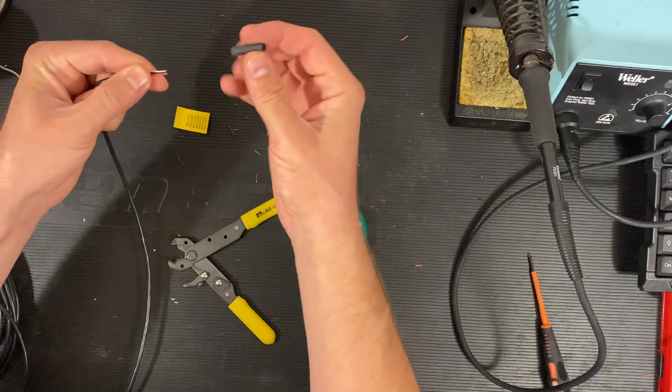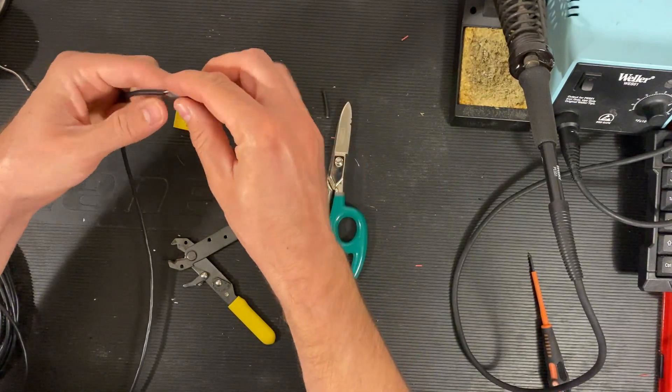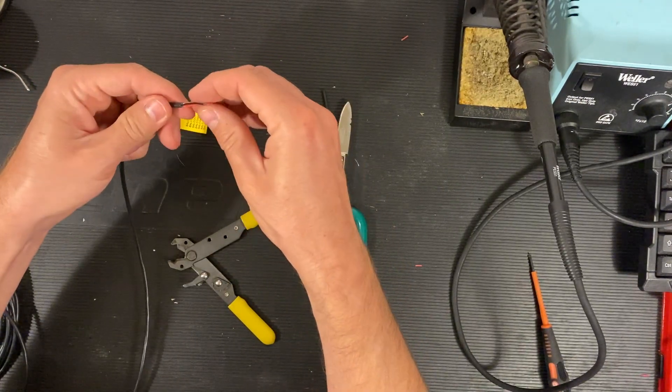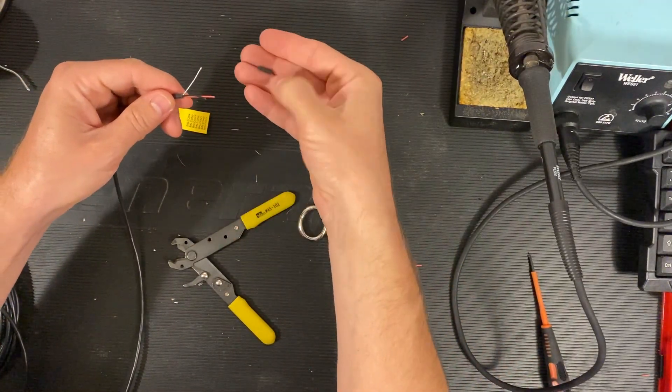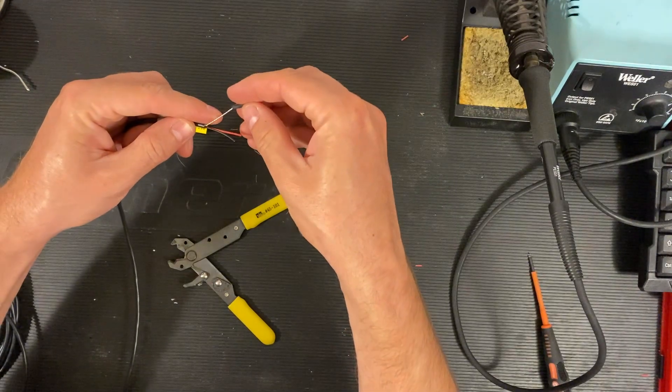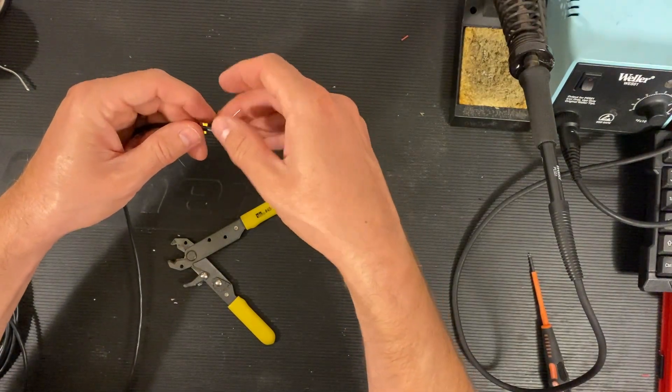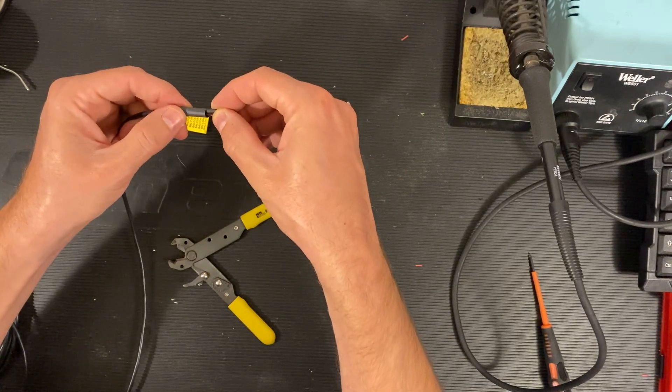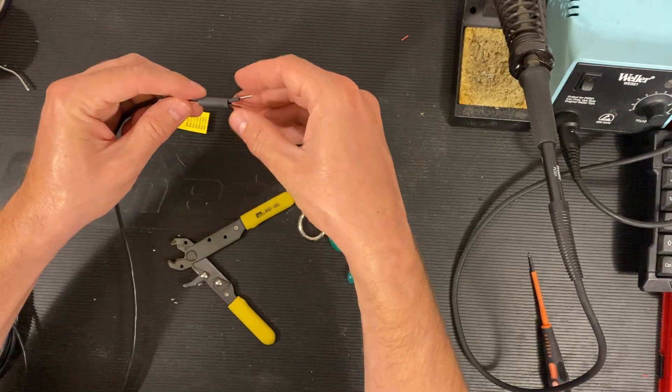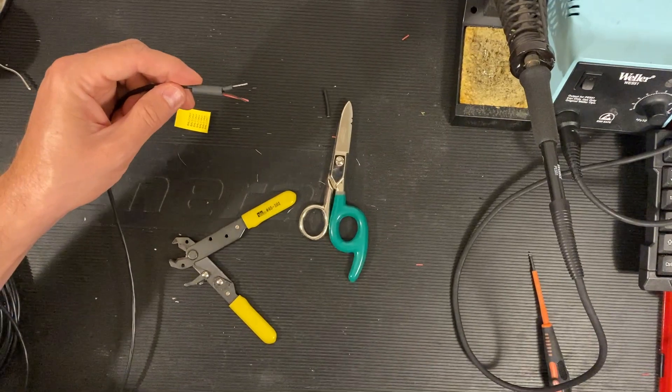We take about an inch long piece of heat shrink and slide it over the conductors. We take a 1/16 inch heat shrink and slide it over the drain wire, and then we bring the large heat shrink back up to where it overlaps the inner conductors by about an eighth of an inch.